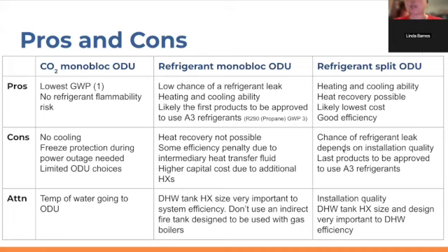On the refrigerant split systems, they are generally the lowest cost systems because you're operating with the fewest heat exchangers possible in order to make a combi system work. Being direct refrigerant exchange, you get generally very good efficiency. As I said in the previous slide, there are refrigerant split topologies that allow heat recovery to happen. And then, of course, being a non-CO2 system, heating and cooling is easily achieved with the common refrigerants like R32 and R454B. Now, refrigerant split systems do require field-made refrigerant connections, and so the chance of a refrigerant leak depends on the installation quality. We really encourage people to go with a reputable installer that warranties their work for a very long time. And then, being a refrigerant split system, you have refrigerant going inside the home.